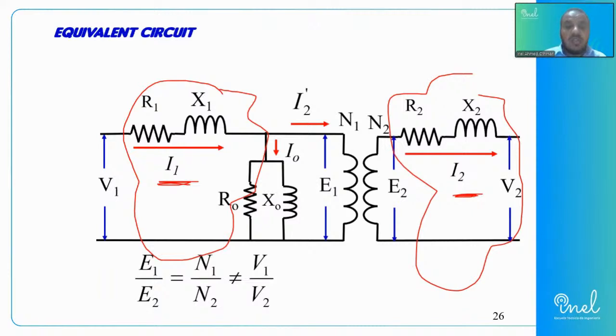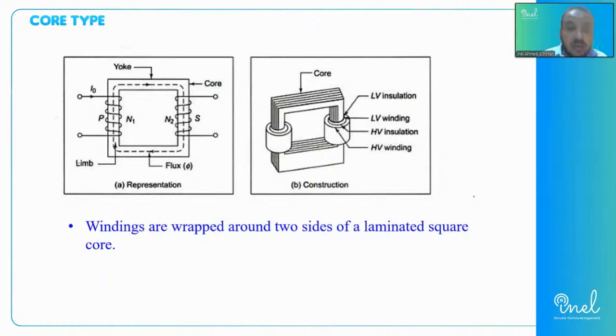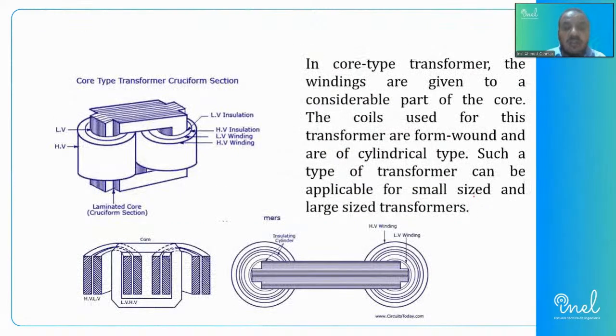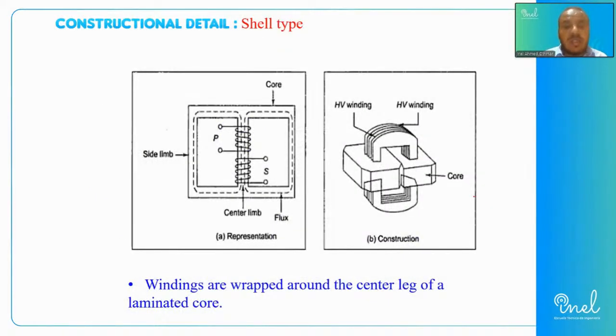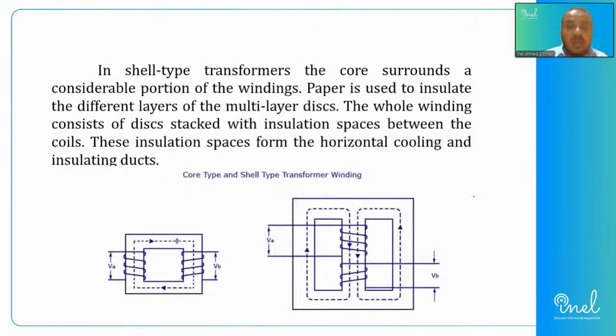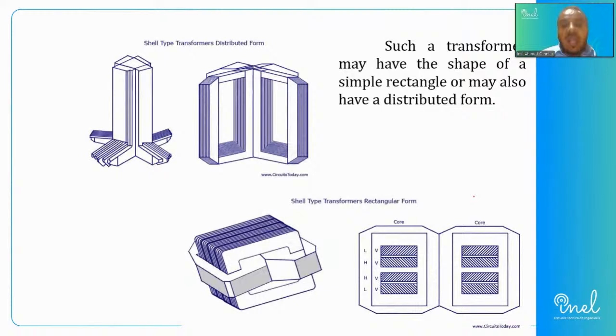Based on EMF equal N1 over N2. There are different shapes of the transformer. We have some of them based on the core and based on the connection. So we have some called shell and some called core type. Core type is where the windings are settled on the core. On the other side, we have shell type, where there is a mid leg where the windings are placed and settled on them. Those are the two shapes.